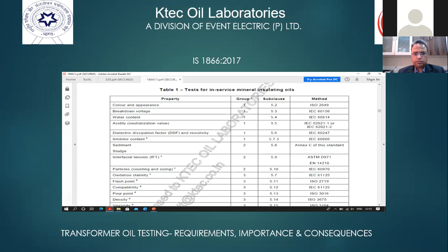Now there are two categories in IS 1866 when we have used the transformer oil. One is whether we have charged the transformer or not, and the second is when we have charged the transformer. That's why there are again two tables. That is Table 3. These are the recommended limits for mineral insulating oils after filling in new electrical equipment prior to energization.